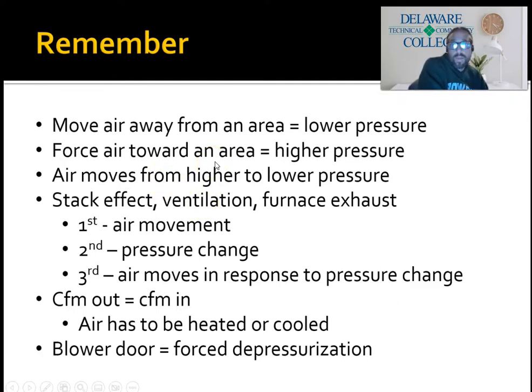Okay, and remember with the stack effect, you have the air that's moving up because warm air is rising, and that creates a high pressure zone up high and a low pressure zone down low. Up high we have high pressure with respect to the outside, and so it's going to push out. In the lower parts of the building, you have low pressure with respect to the outside. That's going to suck air in. So on a really cold day, you may feel a draft along the floor of a building if there are particularly leaky spots, and that's from the air being sucked in because of the stack effect.